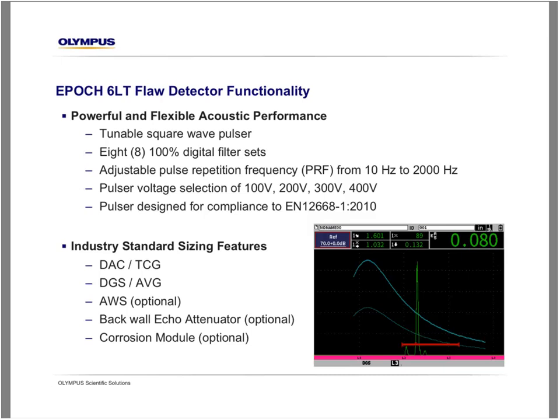The EPOCH 6LT flaw detector, in fact, is based very heavily on the design of the popular EPOCH 650 flaw detector that's been in the market since 2015. So you'll see a lot of commonalities in terms of core acoustic functionality. Things like our pulser power, this is really a hallmark of Olympus flaw detector and EPOCH flaw detector functionality. We do offer a tunable square wave pulser that features very accurate and high power output to transducers, and this is primarily focused on low frequency transducer function. But this tunable square wave pulser is very easy to use.